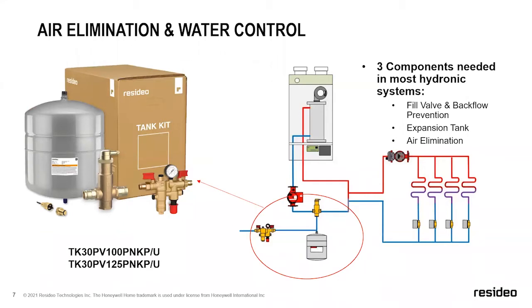And when you look at what goes into a mechanical room, we took 3 components that are in virtually every system and bundled them together to give you a cost competitive package. So you save a little bit of money by buying them as a package, but every system needs to have some form of air elimination, an expansion tank, as well as a fill valve and backflow.